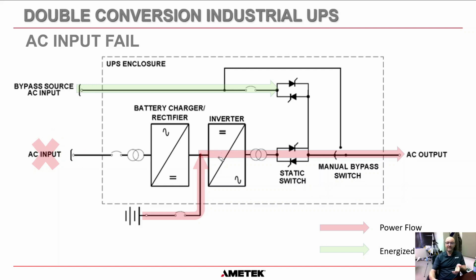Now, most UPS manufacturers have some form of ability to disconnect the battery if the battery discharges too far. So if this power failure goes on for too long and discharges the batteries, in most circumstances it's down past 1.75 volts per cell for a lead acid battery, and for a 60 cell battery that would be 105 volts DC. So we have a tripping mechanism within our system that says, okay, my battery has got to 105 volts DC, I need to do something about it. And on the next page, I'll show you exactly what happens.